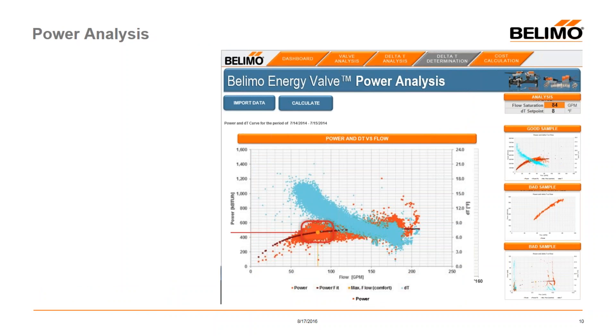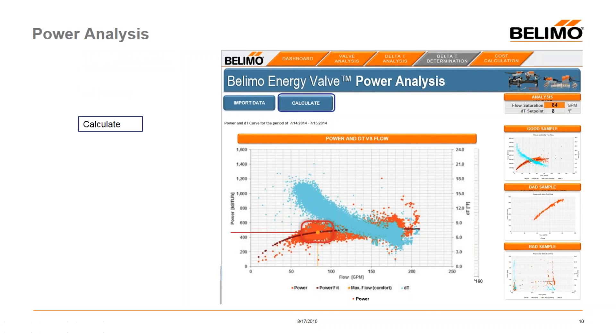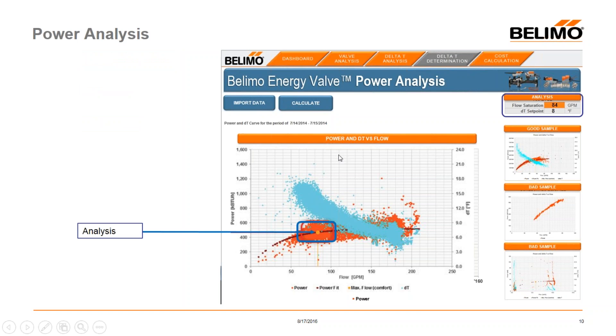The next tab is the Power Analysis tab, which determines the capabilities of your coil. From here you can import a different data set, change the date range, or anything else you need, then click Calculate to generate these curves. The power curve, shown as a red line, indicates that at around 8 degrees delta T and approximately 84–85 gallons per minute, the coil BTU output is maxed out. Increasing flow and GPM beyond that point gives no additional BTU output — this is what we call the saturation point.